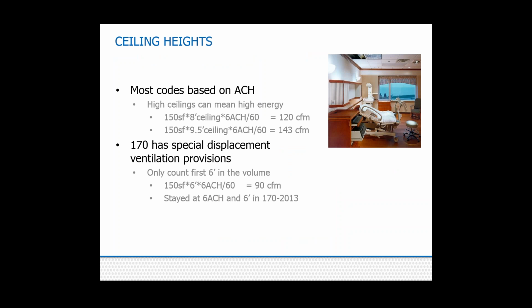So another thing, at least during design, that you have some control over is ceiling heights. I mean, everybody loves a tall ceiling and nice daylight and views and so forth, but our ventilation requirements are usually, in most codes, based on air changes. So just for a code minimum 150 square foot patient room with an 8-foot ceiling, I do an example saying that requires 120 CFM of flow, whereas with a 9.5-foot ceiling, it's 143 CFM. And often that air is being cooled to dehumidify it, plus it's being reheated to avoid overcooling the room, depending on what time of year it is.